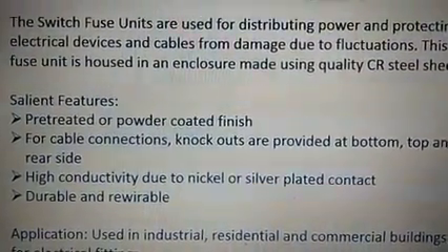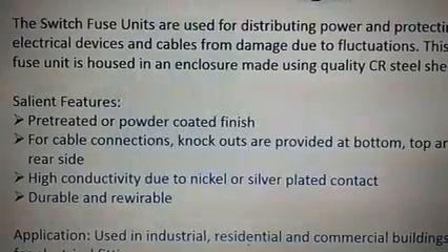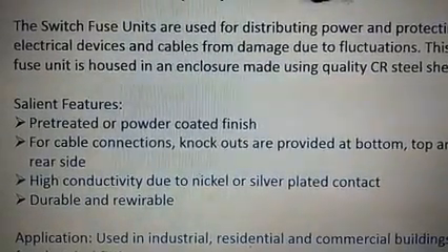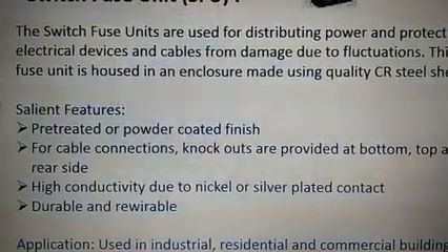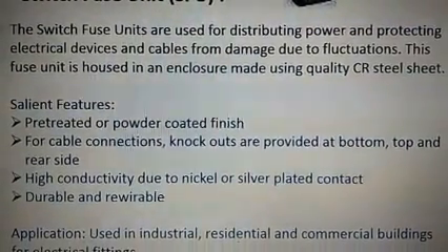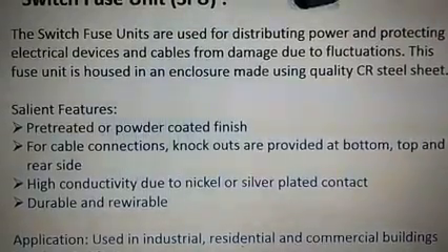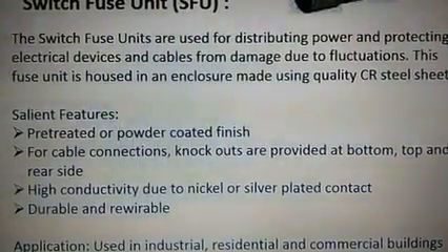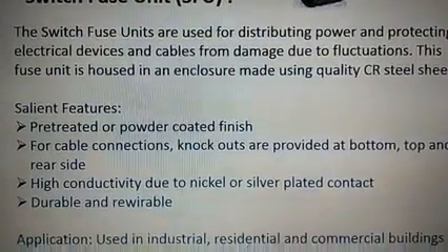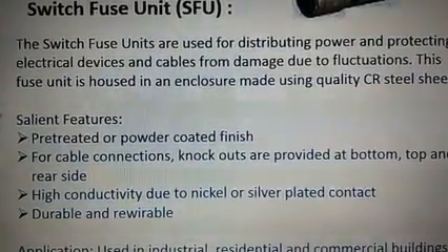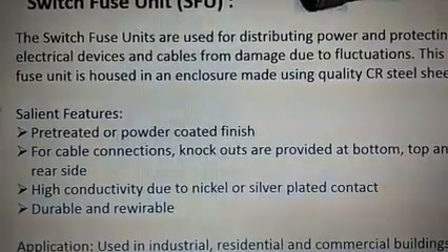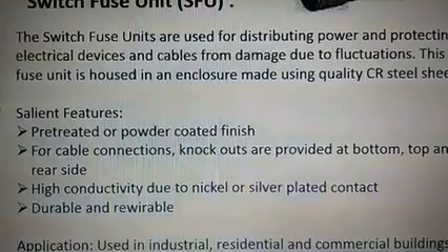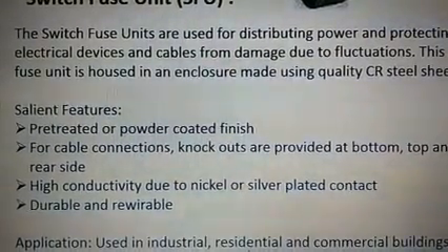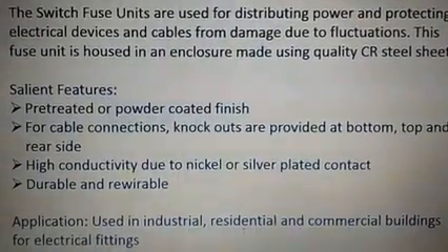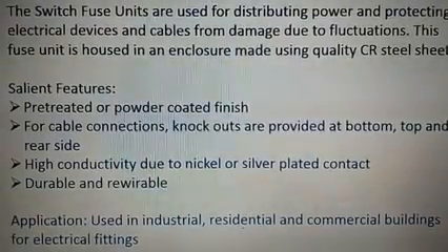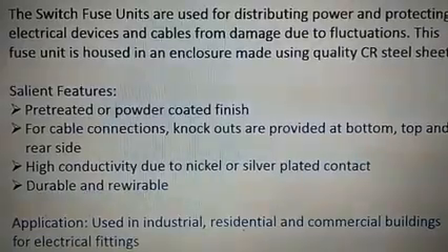The features of this SFU are a pre-treated or powder coated finish. For cable connections, knockouts are provided at the bottom, top and rear side. There is high conductivity due to nickel or silver plated contact at both ends, and hence it is very durable and rewirable. It can be repaired in industry again. You can reuse the fuse.